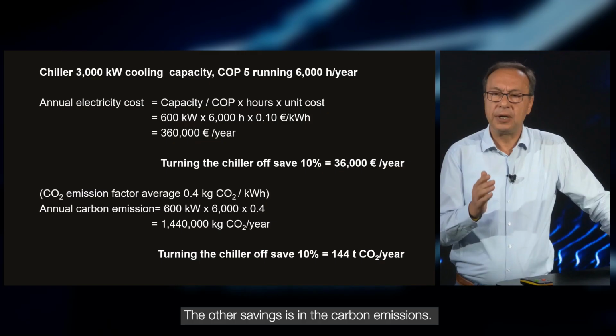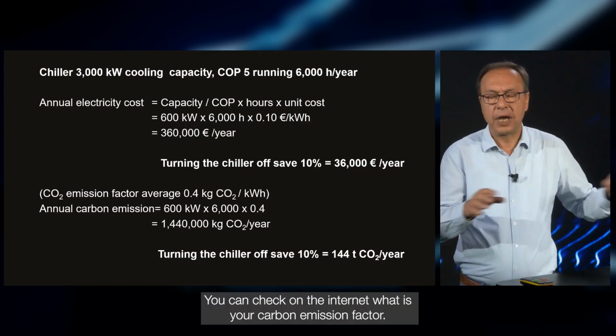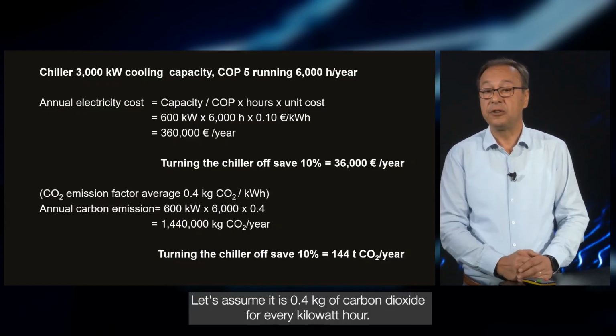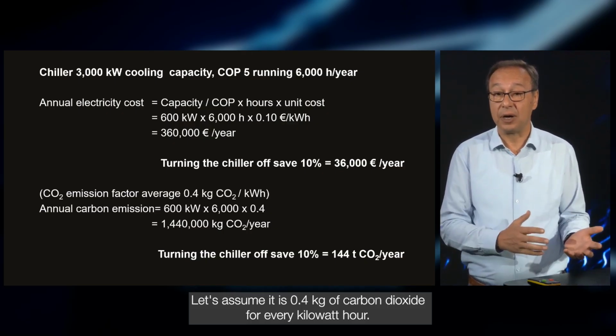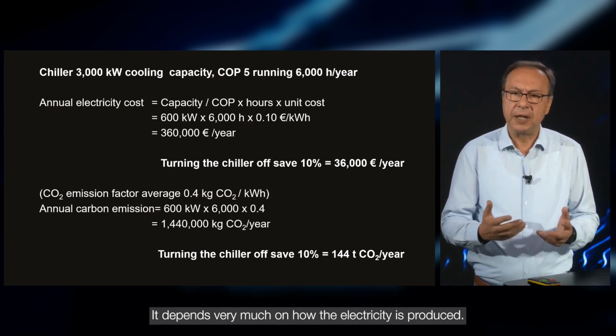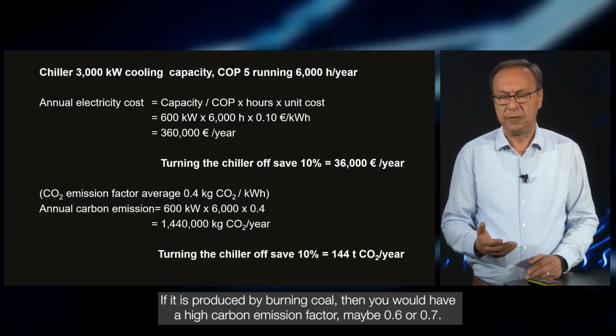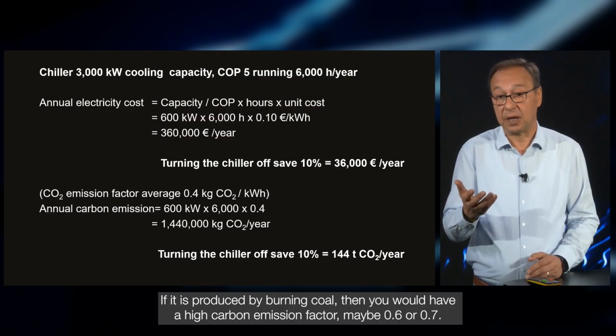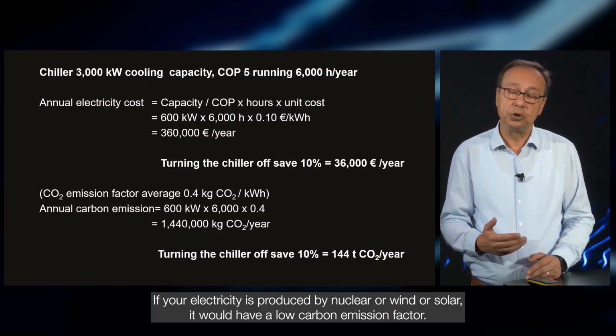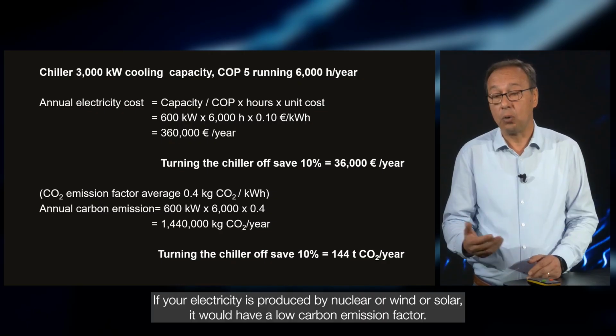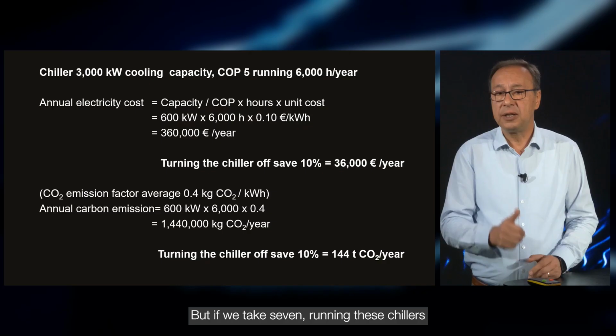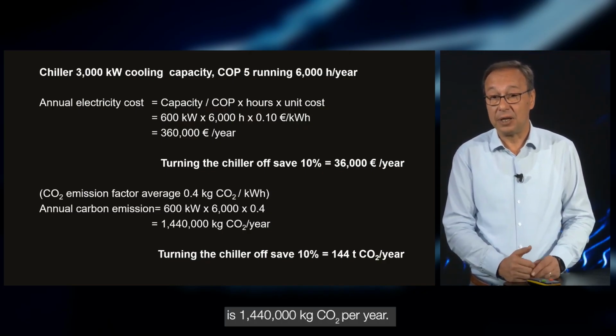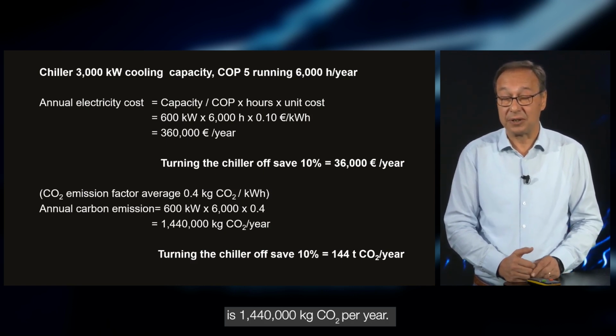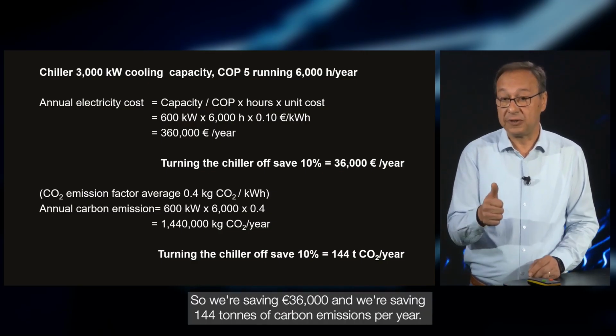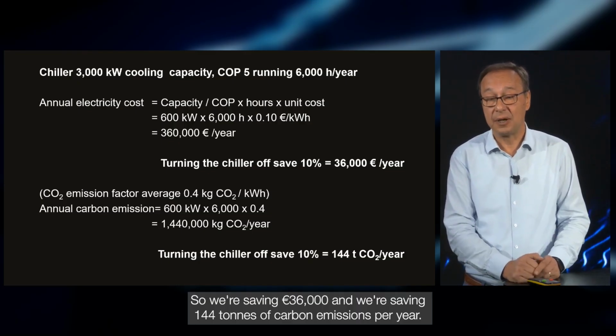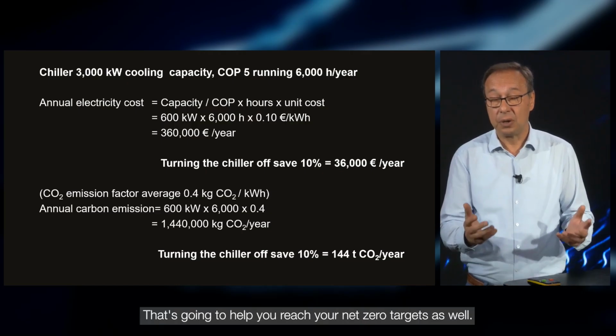The other savings is in the carbon emissions. You can check on the internet what your carbon emission factor is. Let's assume it is 0.4 kilograms of carbon dioxide for every kilowatt hour. It depends very much on how the electricity is produced. If it is produced by burning coal, you would have a high carbon emission factor, maybe 0.6 or 0.7. If your electricity is produced by nuclear, wind or solar, it would have a low carbon emission factor. If we take 0.4, running this chiller 6,000 hours throughout the year is 1,440,000 kilograms of carbon dioxide per year. So we're saving 36,000 euro and 144 tons of carbon emissions per year, and that's going to help you reach your net zero targets as well.